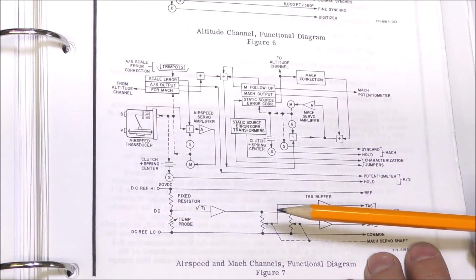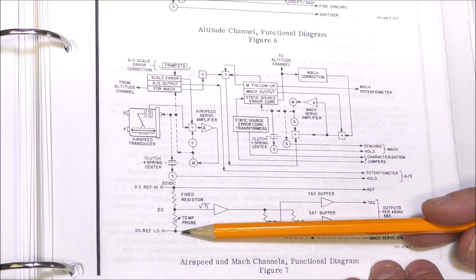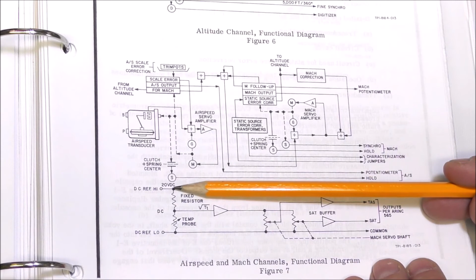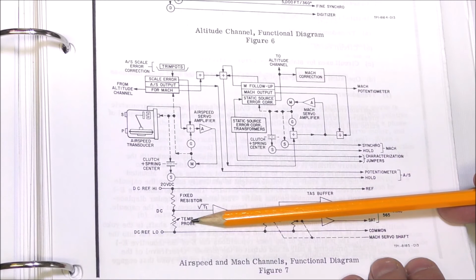So we have on the bottom of this page the block schematics of the measurement of the temperature. The probe actually is a platinum sensor, I think it's 500 ohm. And there is a resistor here and also a reference voltage here. Due to the specific function of the resistance versus temperature, the voltage at this point is close to the square root of the absolute temperature.